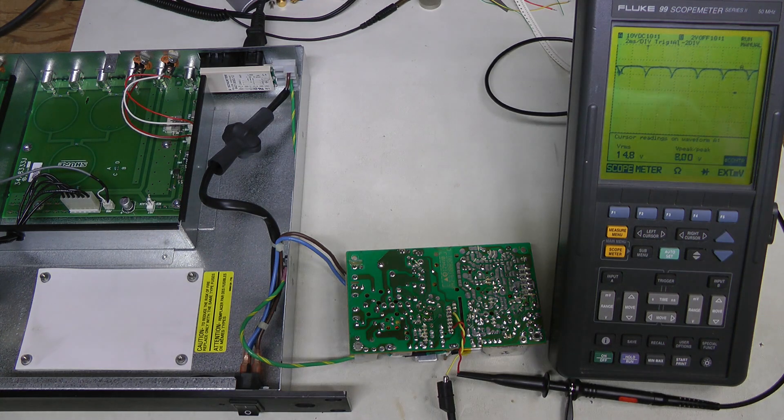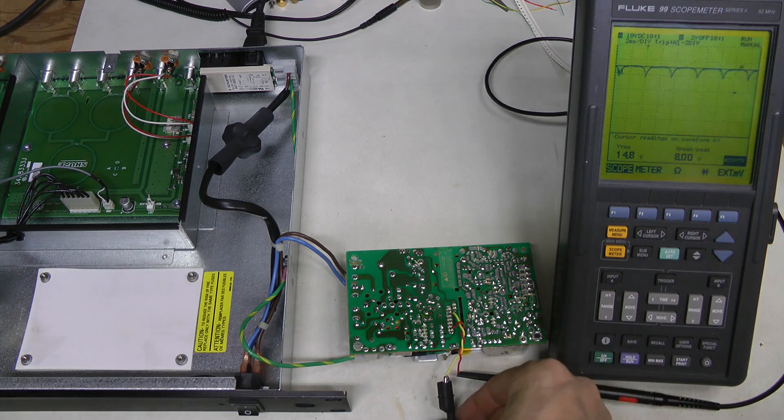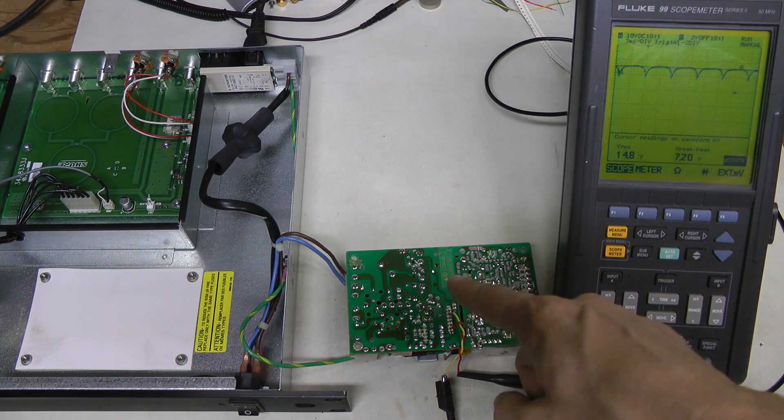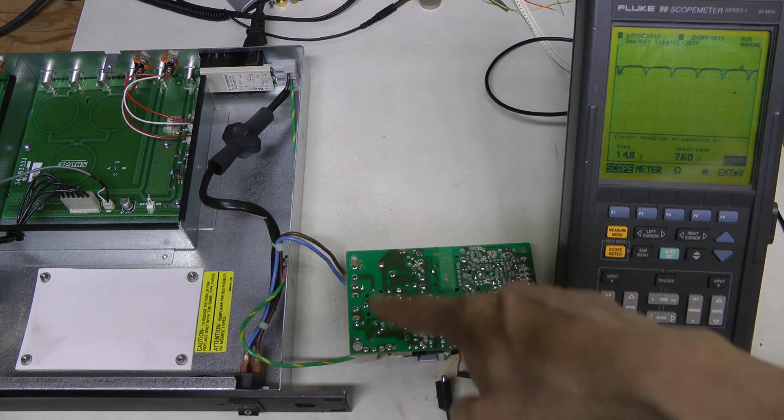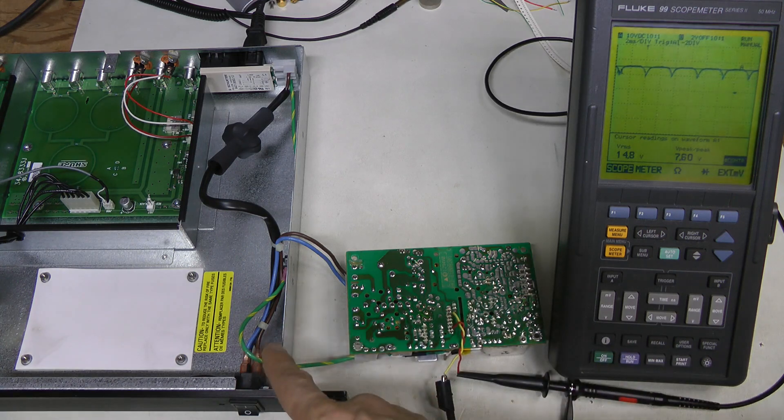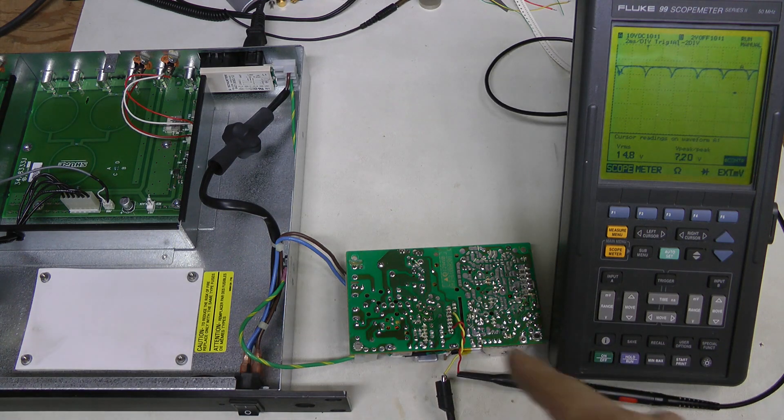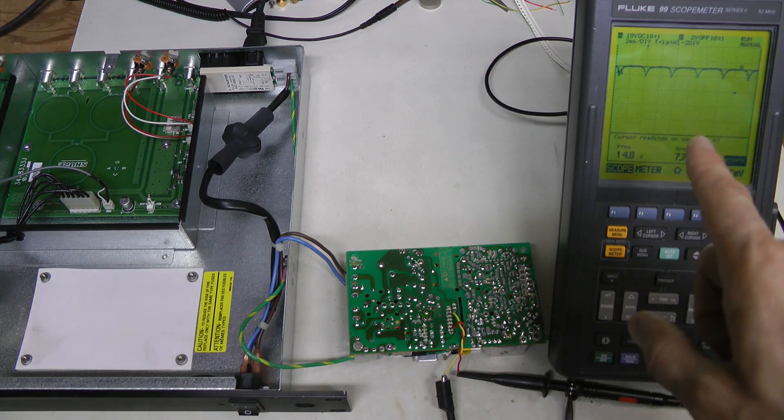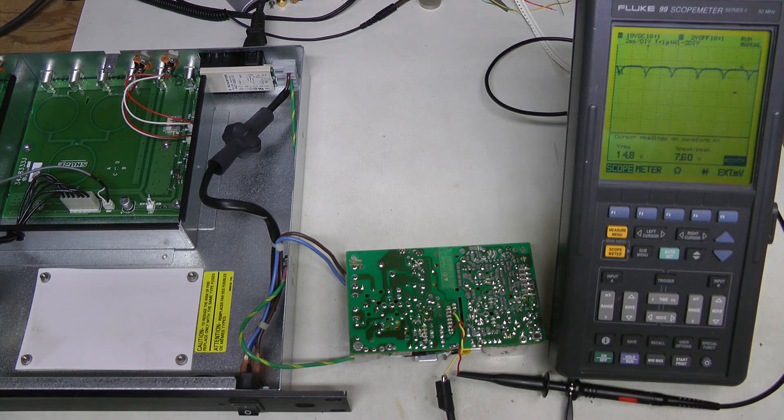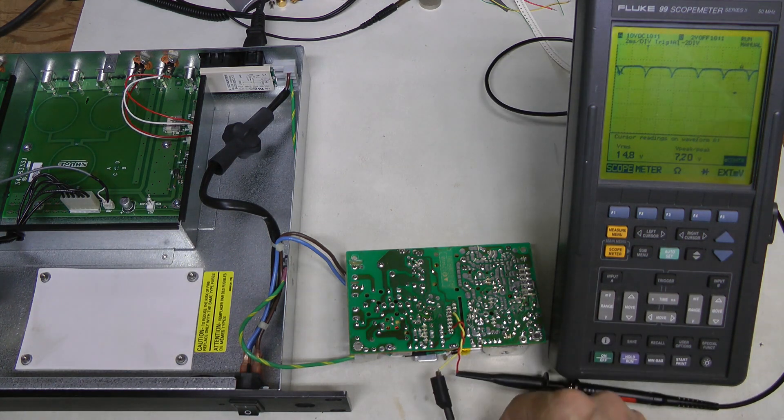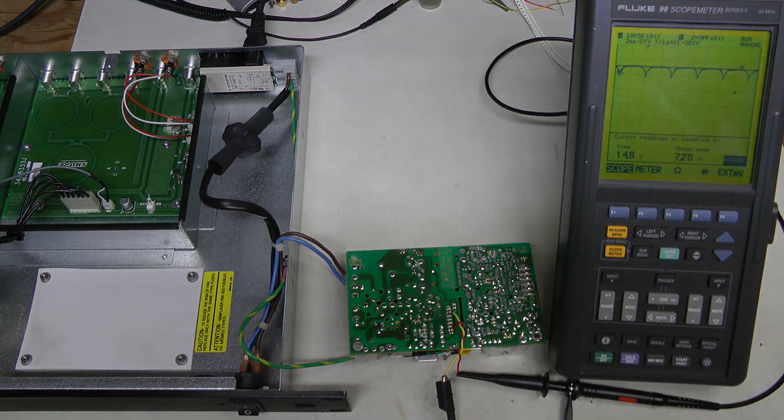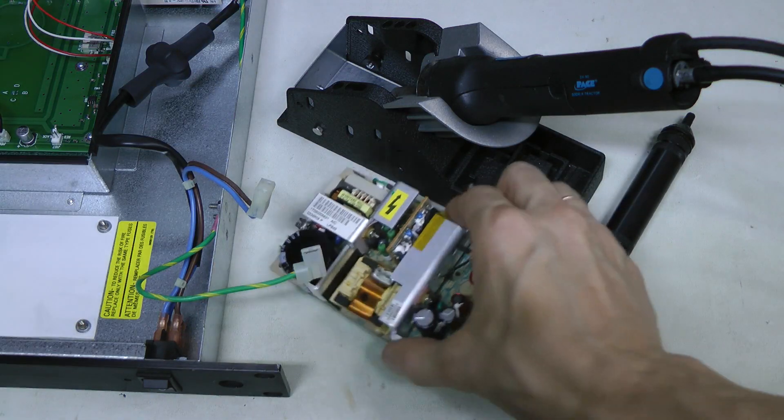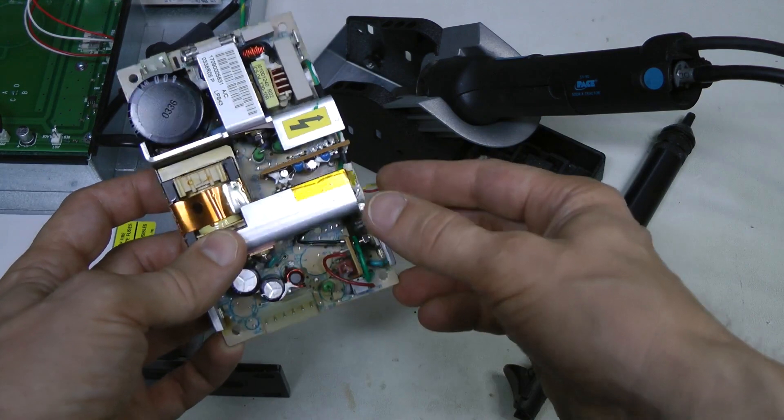And let me repeat once again that this alligator clip is connected to so-called common ground here on the primary side. But it's not the same as this earth ground at all. And I can do this here because this is an isolated oscilloscope. Don't try this with your regular oscilloscope, which is earth-referenced. You are going to melt this ground lead or something else.